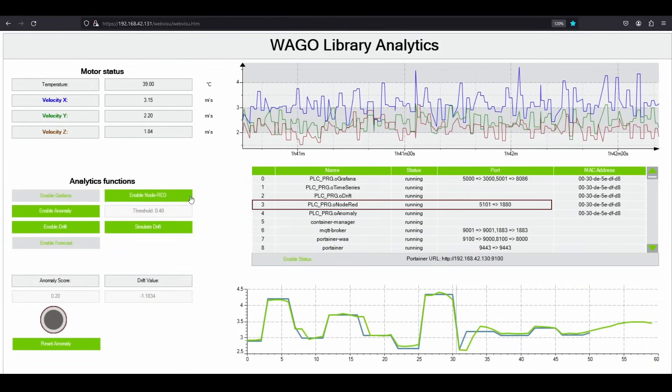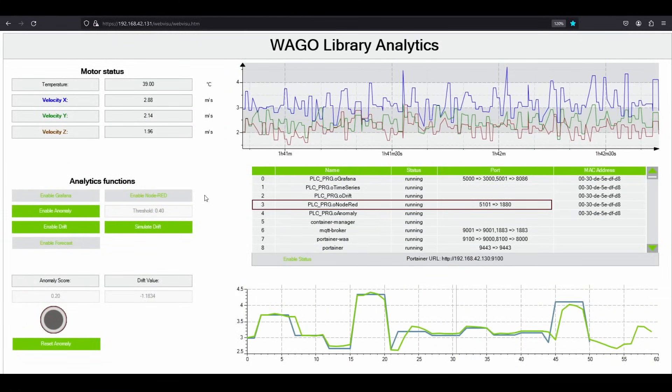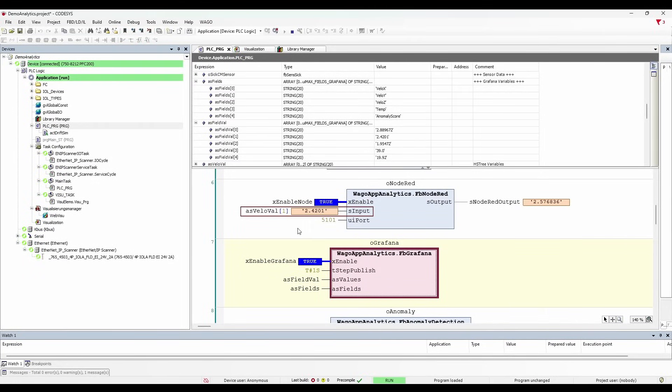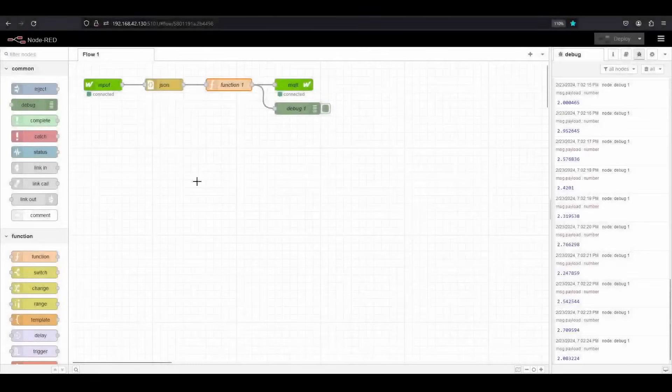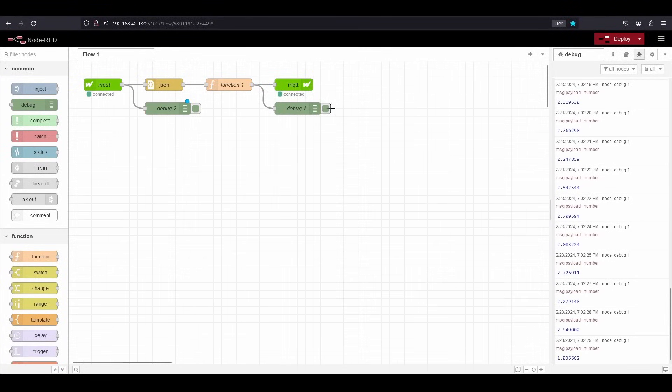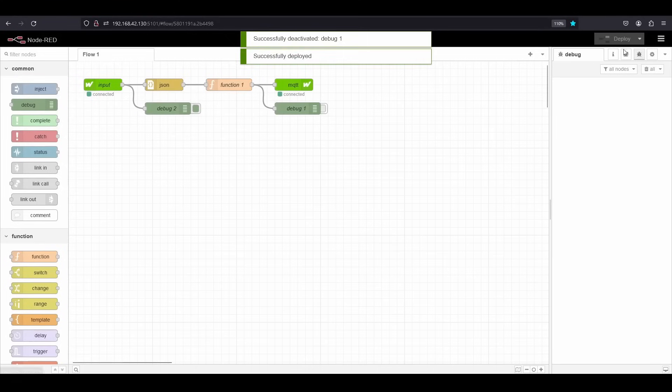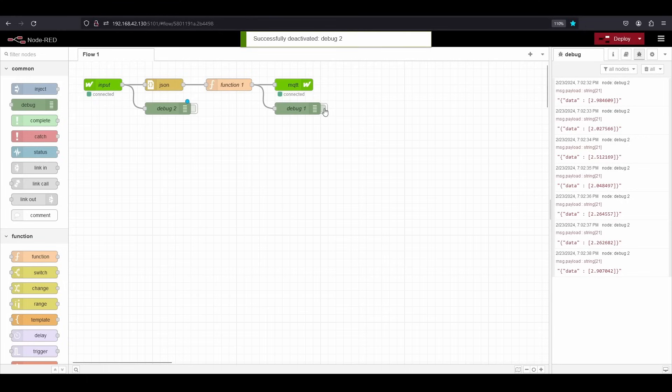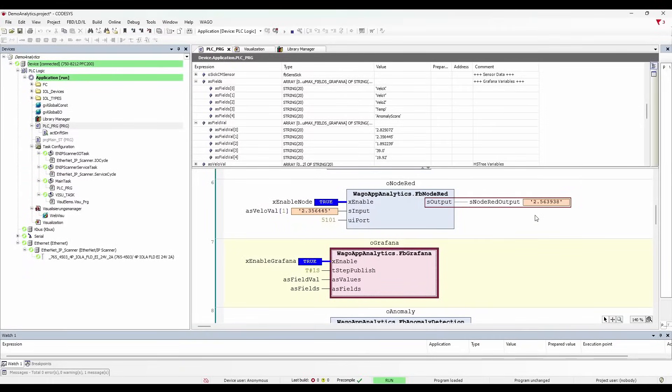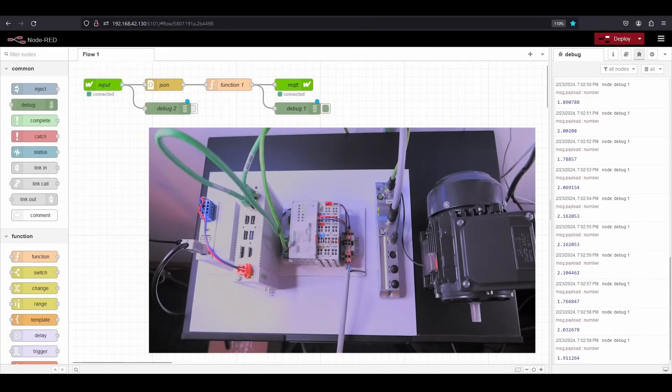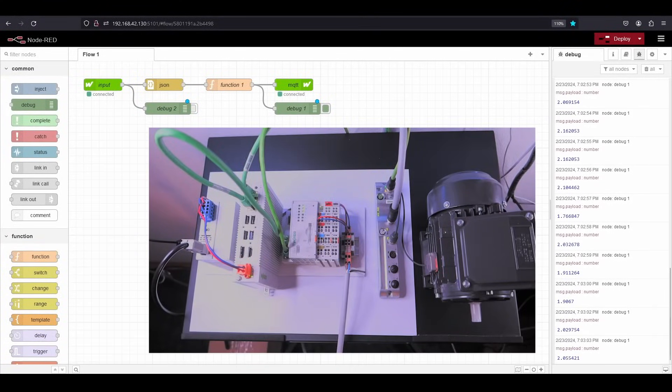Similarly, by enabling the Node-RED service on the Docker container, I can also send data directly to Node-RED. Here, I'm sending only the vibration value on the y-axis. You can view this value using a debug node. The data comes in as a JSON string. Just as an example, I'm extracting the value and sending it back to the controller. So my vibration value is coming as JSON string, which you can see in the debug window. I'm formatting it in the function node and sending it back to the controller as a number. You can see the value coming back to the function block here. If you're familiar with Node-RED, you can imagine the endless possibilities for using the data. One realistic example could be sending your analytical data to cloud services for remote monitoring.